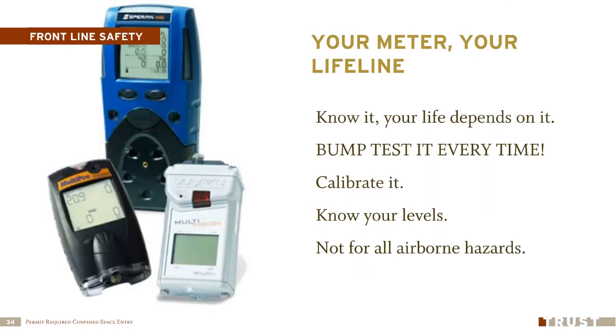Well, it needs to be calibrated. It'll come calibrated from the factory to start with, but you need to verify this every time you use it, and we call that a bump test. I've done a YouTube video on performing a bump test, it's on our channel there, so it's specific to that. I won't spend a lot of time on it because this is a quick video that we're doing today.